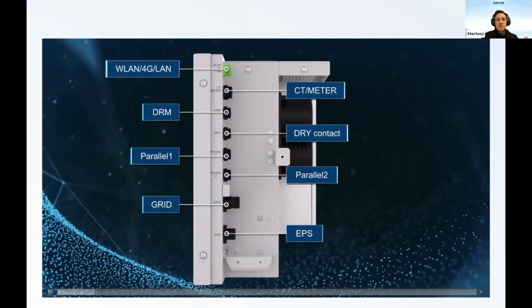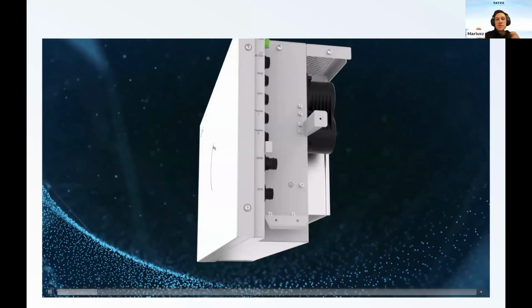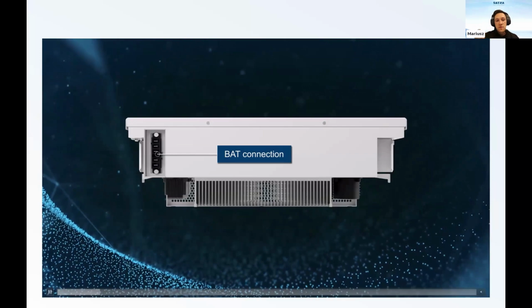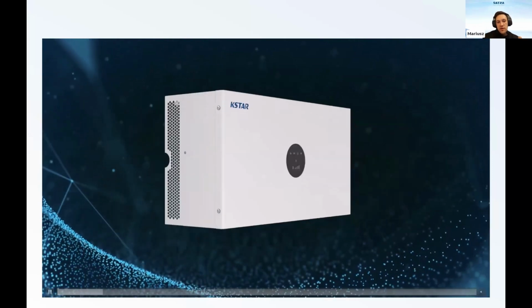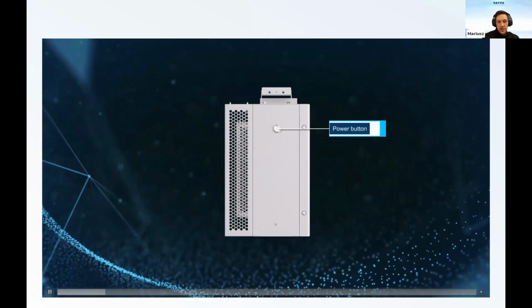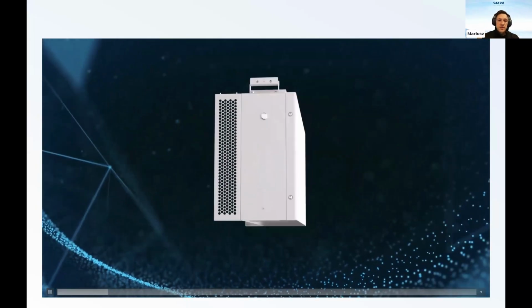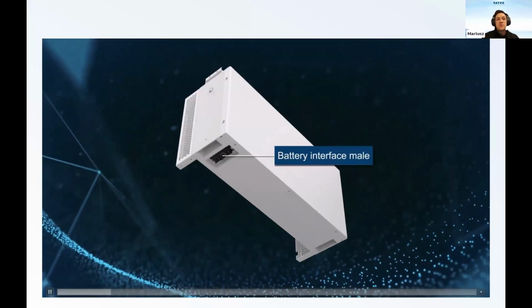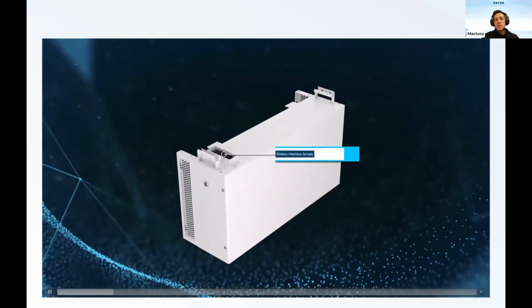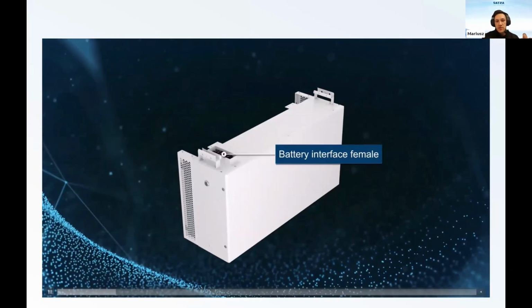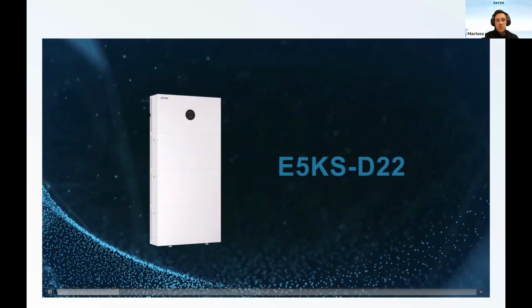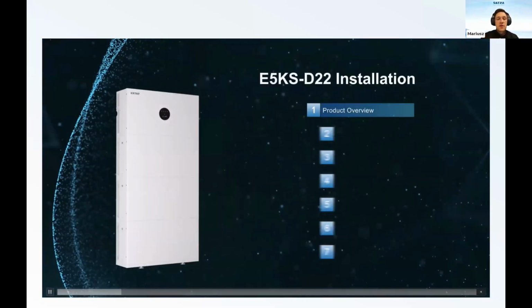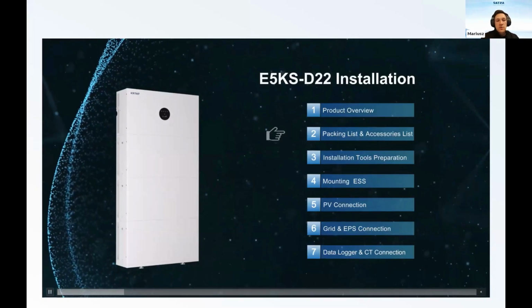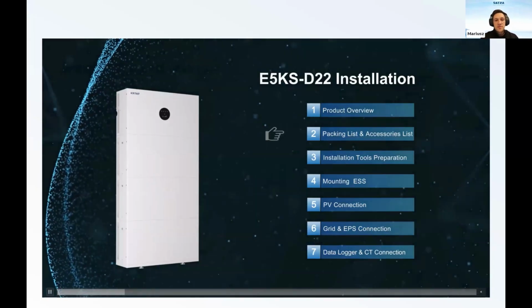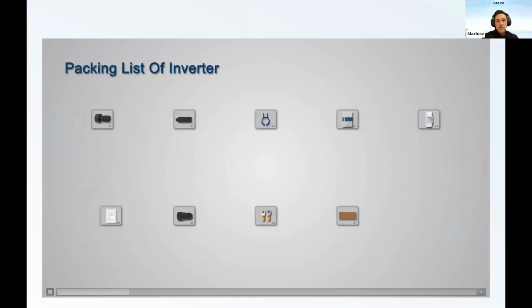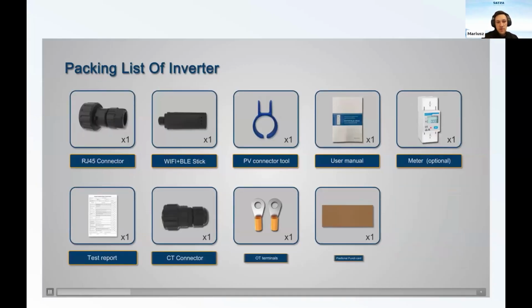We have DC inputs on the left, and AC outputs and the communication interfaces on the right. On the bottom of the battery we have a male connection, and each battery has its own BMS. That's why we can turn on the batteries one by one, or we can turn on the batteries from the inverter. Both ways are similar and equal. This shows us that each battery contains a BMS. So if we have a problem with any one of the batteries, we will deal with it at the module level.